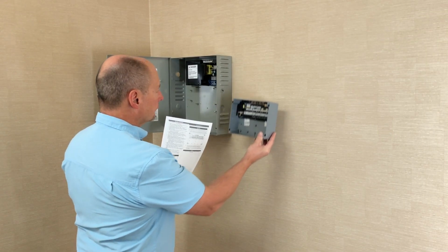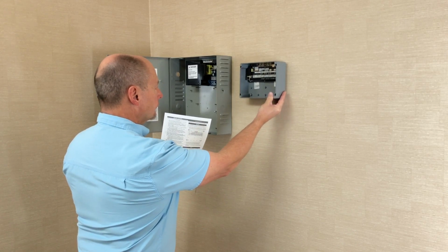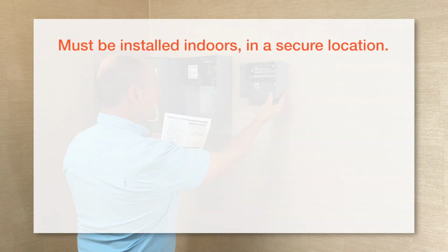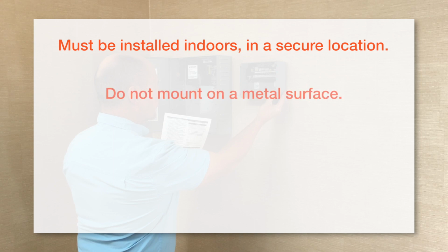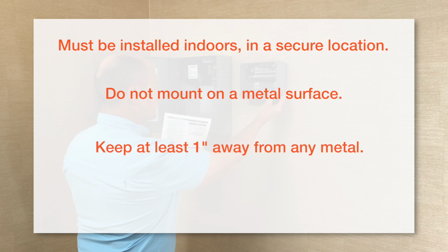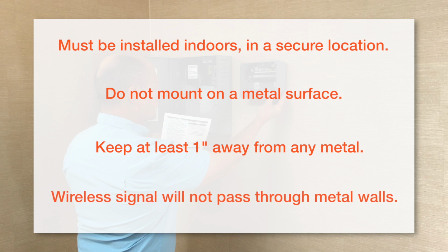Determine the appropriate location to mount the CTE. The CTE must be installed indoors in a secure location. Depending on your system setup, this could be an electrical closet, server room, or in the ceiling above the opening. For best wireless performance, the CTE should not be mounted on a metal surface or positioned within 1 inch of any metal. The wireless signal will not pass through metal walls or metal mesh in the walls. If you are unsure of the building construction, consult your facility manager.